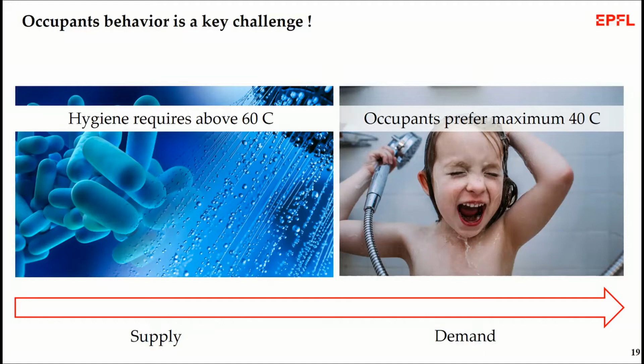Another challenge in the hot water system is that, on the demand side, occupants prefer a maximum of 40 Celsius degrees when they are going to take a shower. But on the supply side, whenever we keep hot water for a long time and in high volume, we need to maintain its temperature above 60 Celsius degrees to ensure that a bacteria called Legionella cannot grow in the water. So there is basically a mismatch between supply and demand in hot water systems.